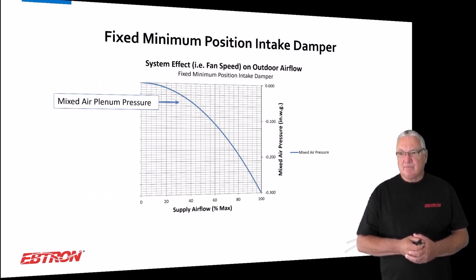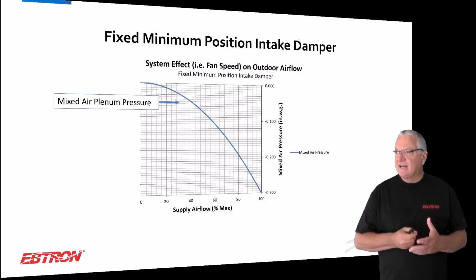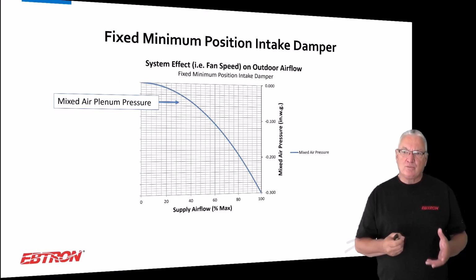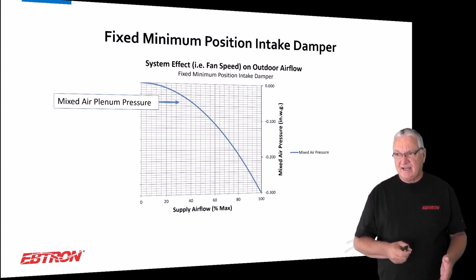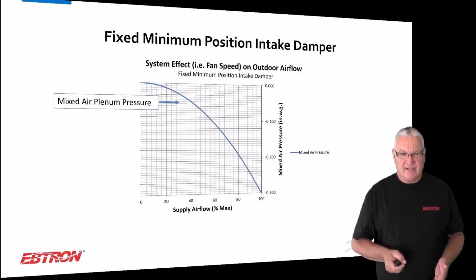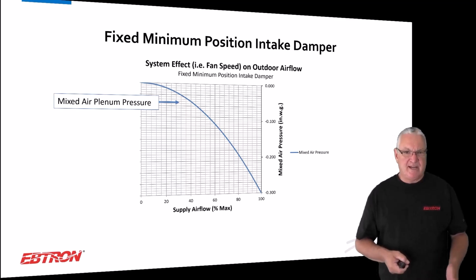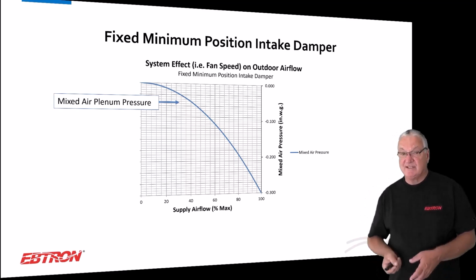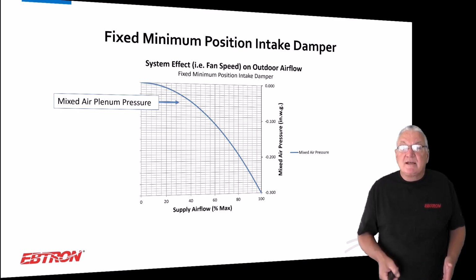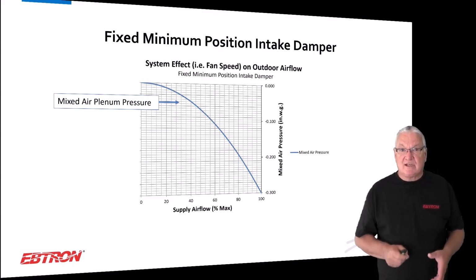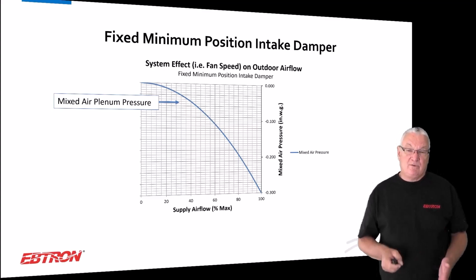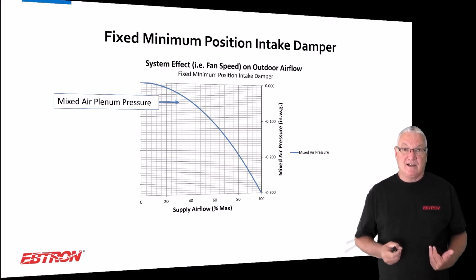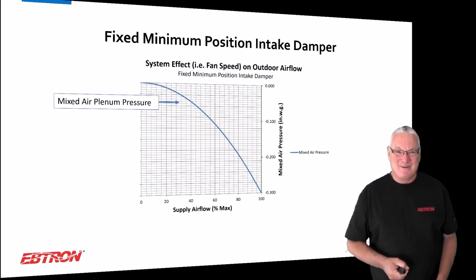And if you looked at the pressure relationship, I'm going to take an example where the total pressure drop across that intake system at design is 0.3 of an inch. That might not be your system. Your system might have a 1/2 inch. Your system might have more than a 1/2 inch. My system might have less than a 1/2 inch. We're going to pick something because we want to be able to have a discussion about it. Although I will say in this format, it's not a discussion. It's just me telling you what I'm going to tell you.